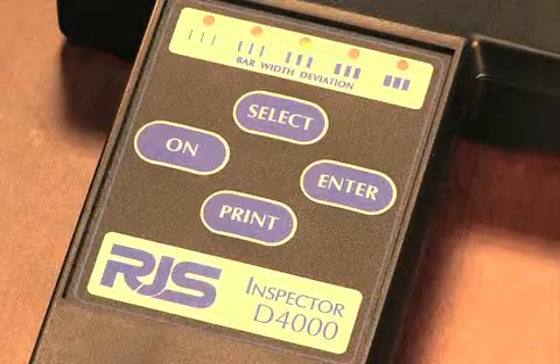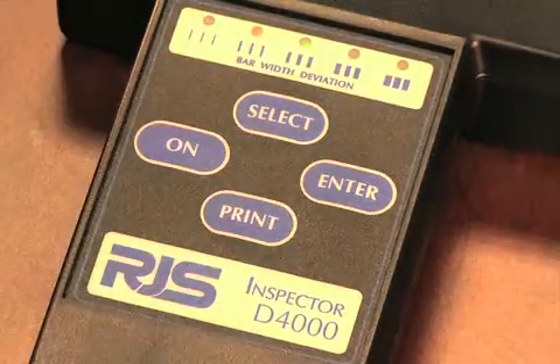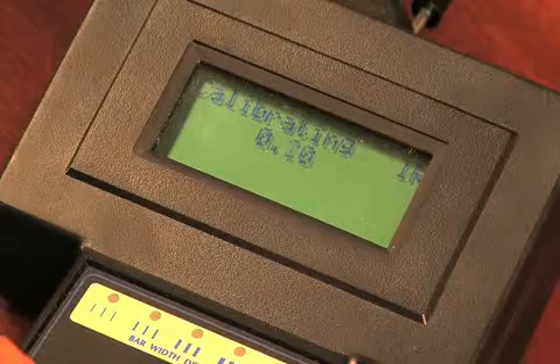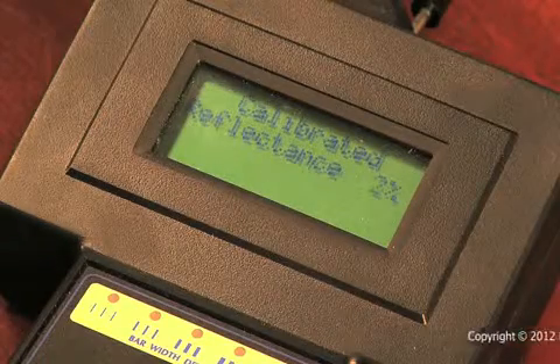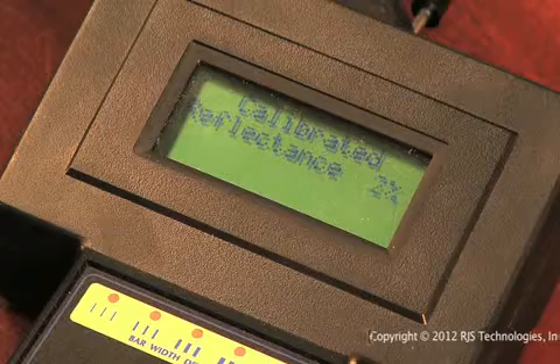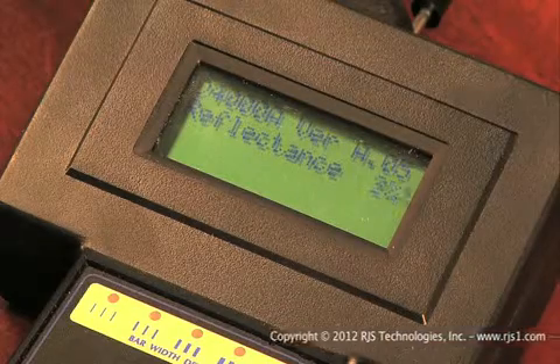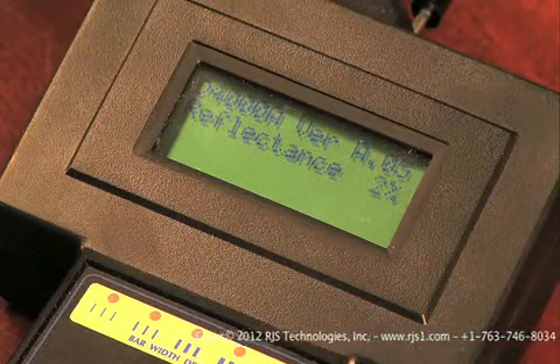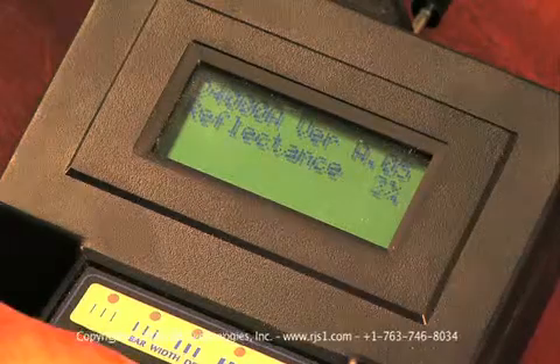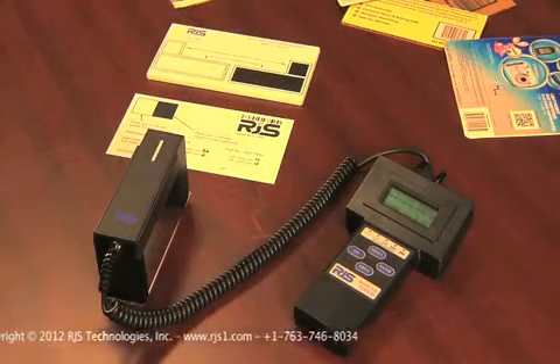Then press the Enter button, and your barcode verifier will repeat the calibration for each of the apertures and light sources for the black value. Following the calibration, check that both the white and black squares are now within plus or minus 2%. If not, repeat the calibration process.